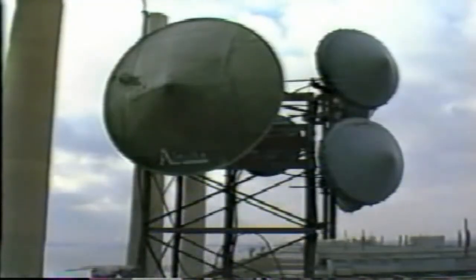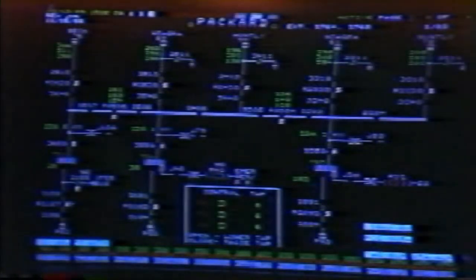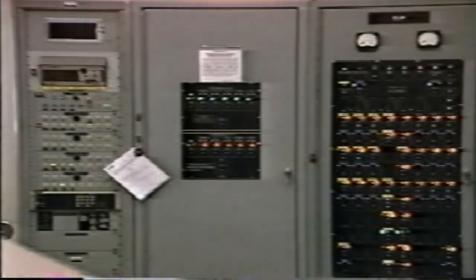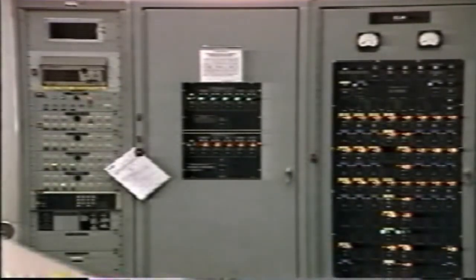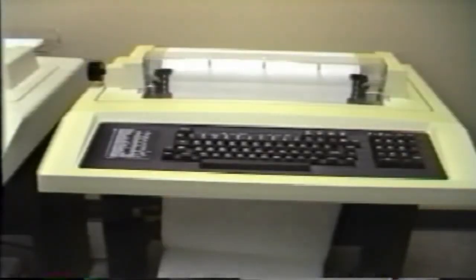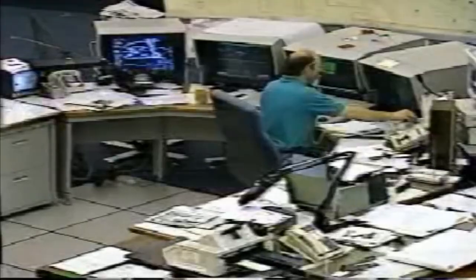In order to carry out his functions efficiently, the system operator must have good communications with the major stations around the system. He also needs minute-to-minute information to indicate the status of the equipment and the conditions at all locations. All of this information is provided in the Energy Control Center. Data is transmitted by telemetry over the various communication networks and is displayed in various forms. For example, the operator reads information from a computer printout, from CRT screens, from recording charts, and from indicating meters.